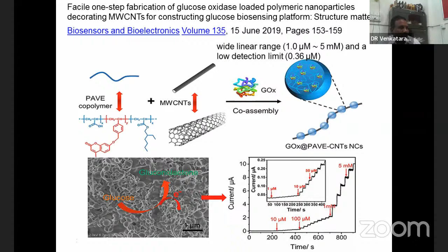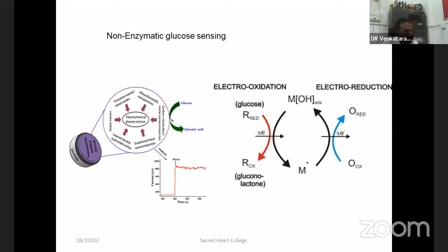So for that purpose also, we try to eliminate glucose oxidase by developing non-enzymatic sensors, where we directly monitor glucose oxidation at a metal, because carbon materials will not undergo oxidation, because of a requirement of higher potential than your metal surface. So we try to use platinum and gold, especially these two materials, along with other transition metals like cobalt and nickel. All materials which are conducting can be used for monitoring the glucose reaction directly without using any enzyme. So here, how the reaction occurs: the sensor metal surface generates oxide hydroxide groups, which interact with the glucose, and it undergoes oxidation to gluconolactone or gluconic acid, or hydrogen peroxide, which are the products formed during the reaction.